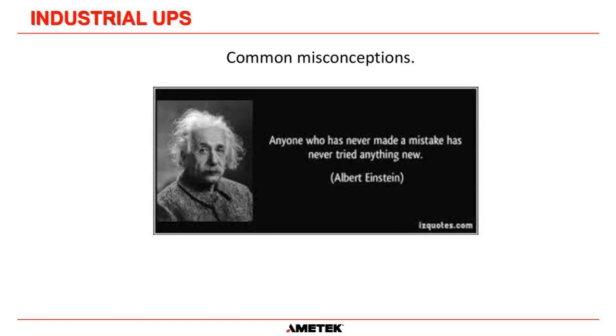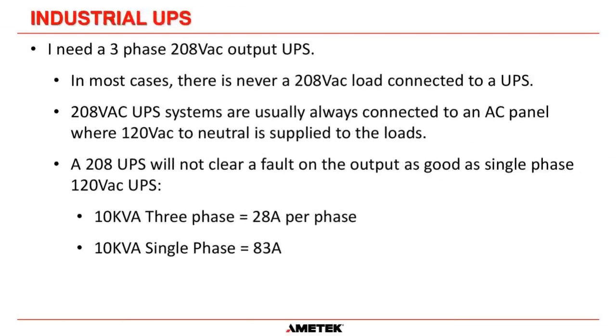Now we'll move on to common misconceptions. The first: 'I need a three-phase 208-volt output UPS.' In 99% of UPS systems we sell, you do not need a 208-volt UPS. There are very rarely 208-volt three-phase loads connected directly to a UPS. In 99% of cases, the 208 goes to a distribution board and you use the neutral to get 120 volts single-phase out of that board.